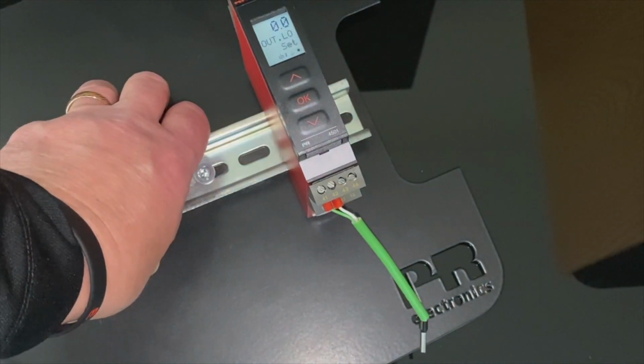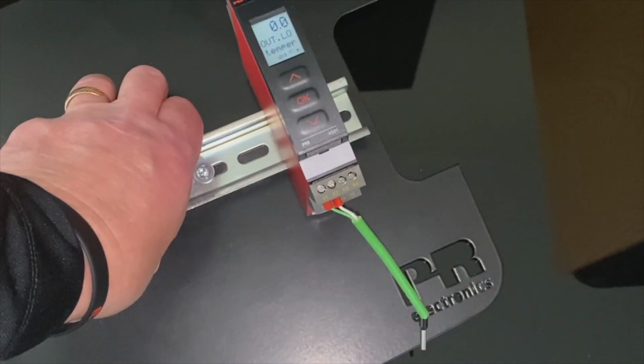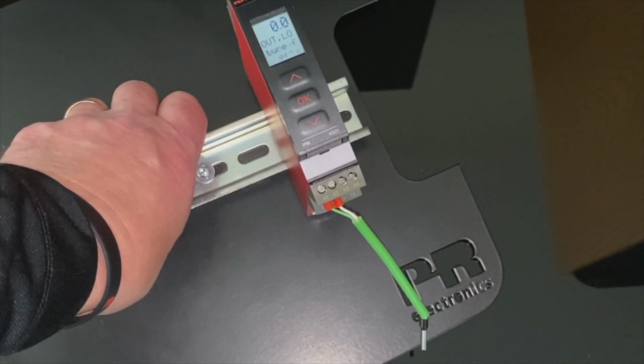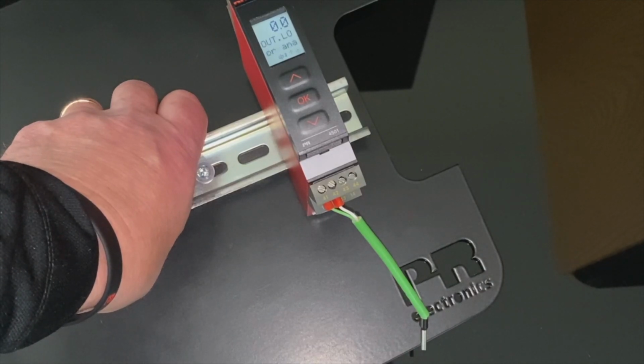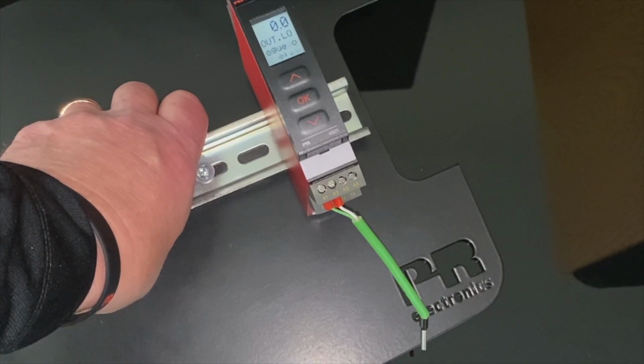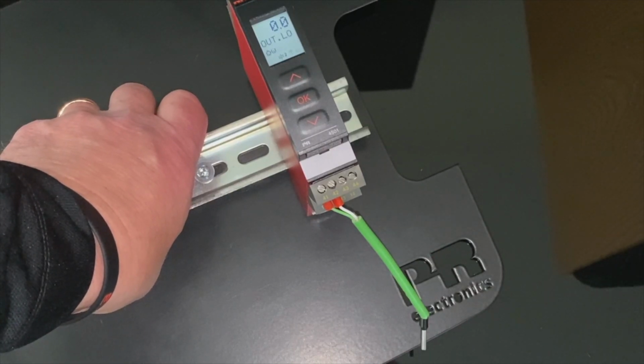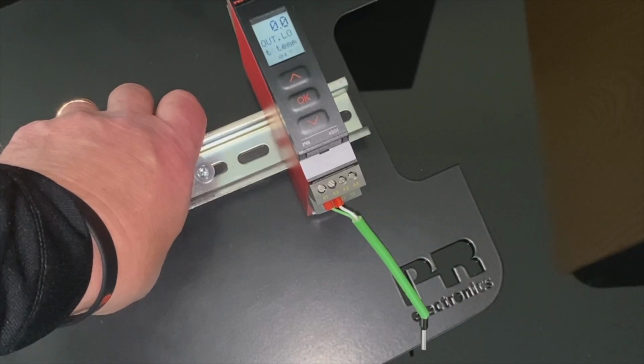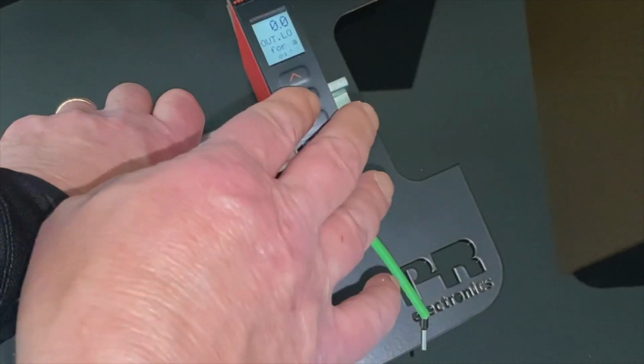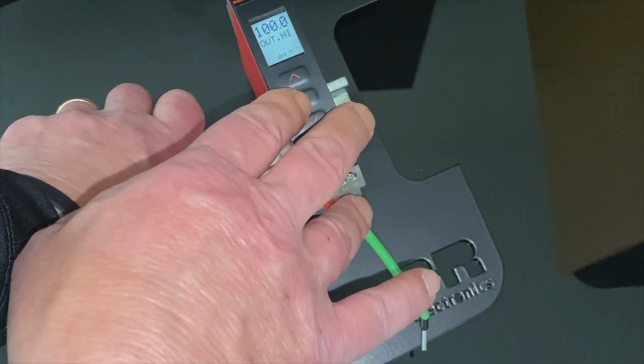And here's where you would do your scaling. You're basically telling the 4116 what is 4 equaling and what is 20 equaling. So that way you can take a big span, if you have a minus 200 degree thermocouple to 1,000 degrees, and you have a real sweet spot that you want to look at, you can narrow that range by just selecting your low and your high.